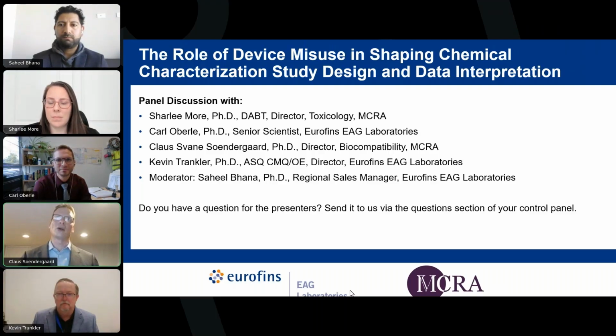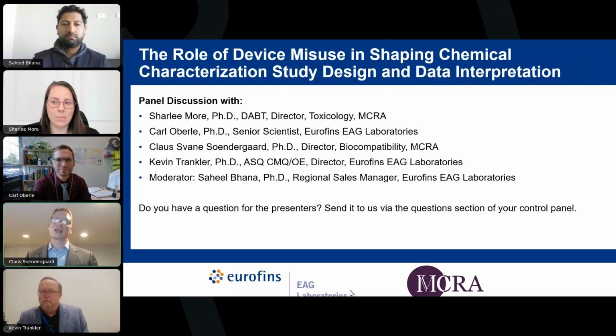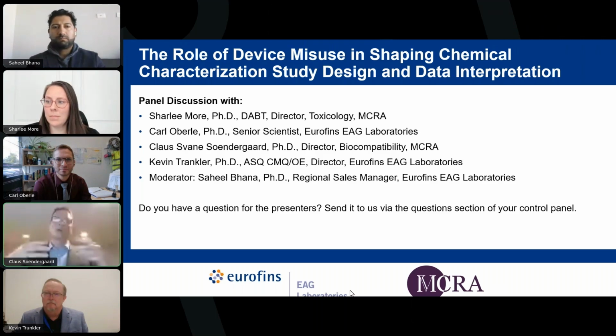Don't come in with open-ended questions. Be very specific, or else you risk getting a laundry list of requests if you're not being proactive. And I'd say that really goes for a lot of your biocompatibility evaluation plan. If you communicate that to regulators, you're the expert on your device. You should be informing them of the outcome of your risk assessment and what is reasonable in your opinion. Here's what I'm going to do, and then the question is, does FDA or a notified body, whoever you're talking to, see anything that is not covered here, rather than asking them to mention other things I should do? So that would be my advice.